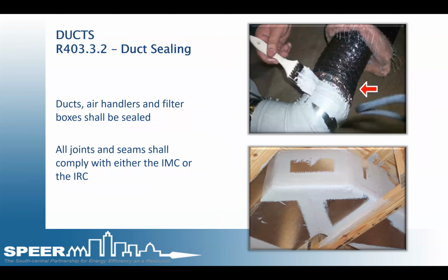On to the next thing, ducts. R403.3.2, duct sealing. All ducts, seams, air handlers, filter boxes and plenums must be sealed, and joints and seams must comply with either the IMC or the IRC on proper sealing. The IECC does not specifically specify how it needs to be sealed. It just says it has to be sealed. It doesn't tell you the material that needs to be used, the thickness, the zip ties, the panduits, however it needs to be done.